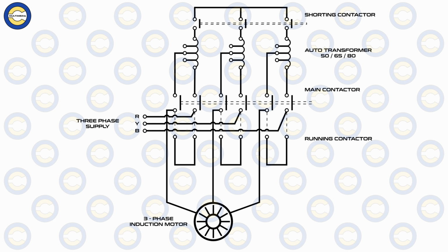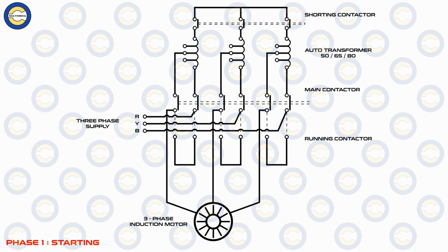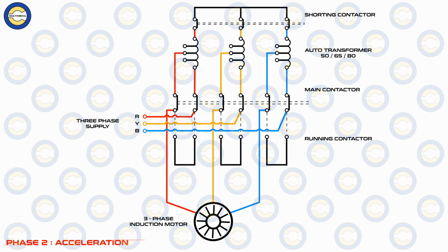To further understand this, let us also correlate a typical working sequence of an auto transformer starter based motor circuit. So let us go through it step by step. In the first step, that is the starting period, when the start button is pressed, the main contactor and the shorting contactor will close. The auto transformer will reduce the voltage applied to the motor's stator. So for example, if the auto transformer tapping is at 65%, then the motor gets 0.65 times the rated voltage per phase.